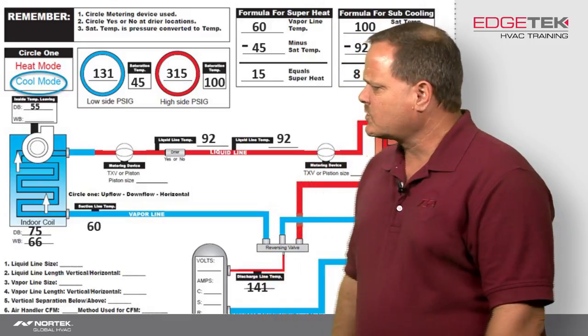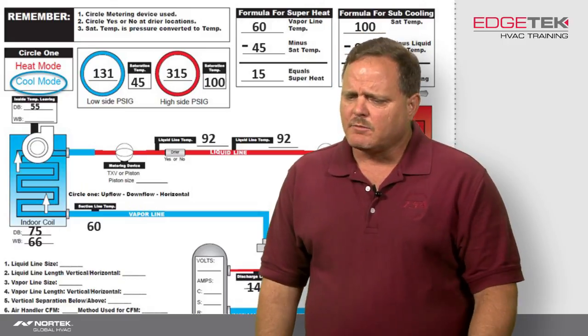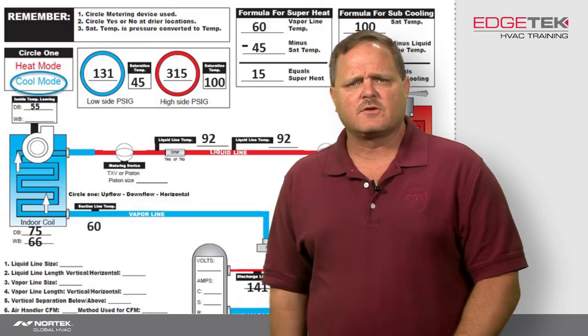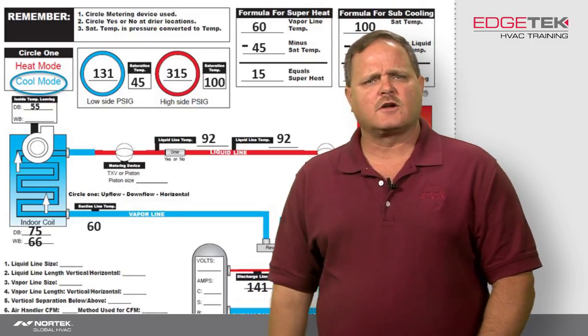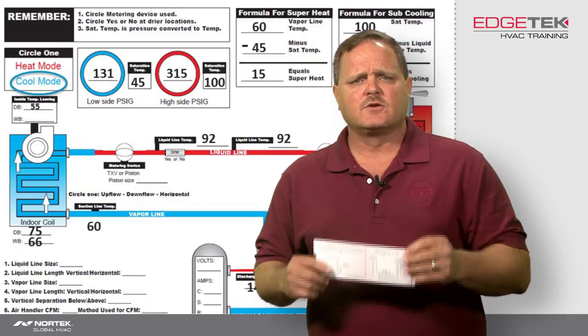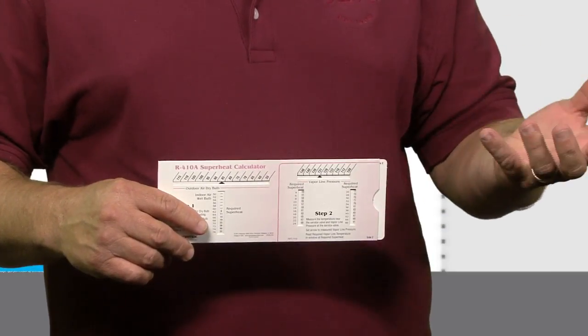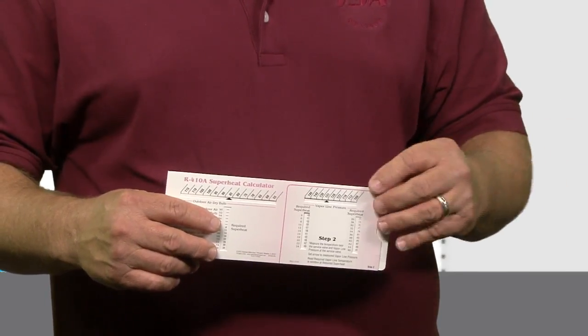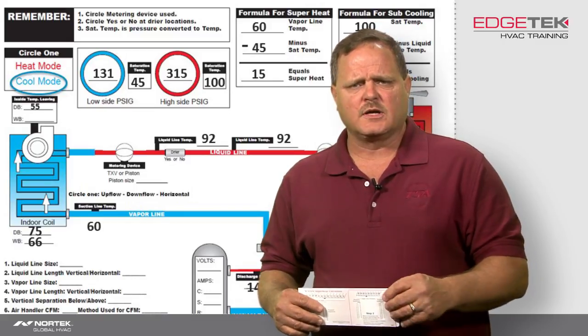The examples we're talking about today are going to be with a piston metering device. In order to troubleshoot a piston metering device properly, you've got to know what that required superheat is. The only way you're going to get that required superheat is by using a slide calculator. You can use Emerson's Charge app — there are a couple different ways to do it — but you've got to have that indoor wet bulb temperature and that outdoor dry bulb temperature, and then under the load conditions, be able to determine what your required superheat is.